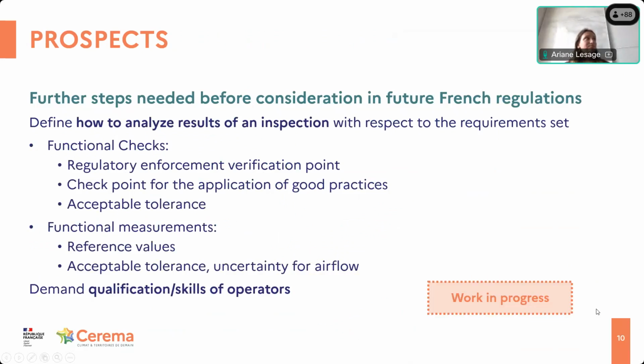And now the next step maybe would be to use PromevenTertiaire in a future French regulation, potentially, but it needs further steps before this is considered possible. So we need to define how to analyze results of an inspection with respect to the requirement set. As for functional checks and functional measurements, for functional checks, there are regulatory enforcement verification points, checkpoints for the application of good practices, and acceptable tolerance in order to conclude with the check.